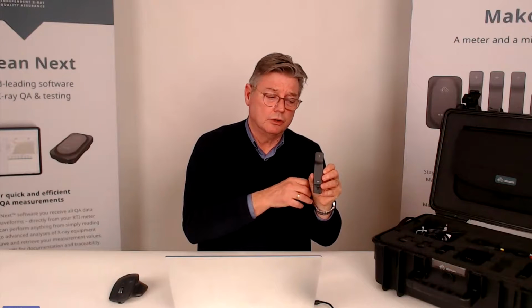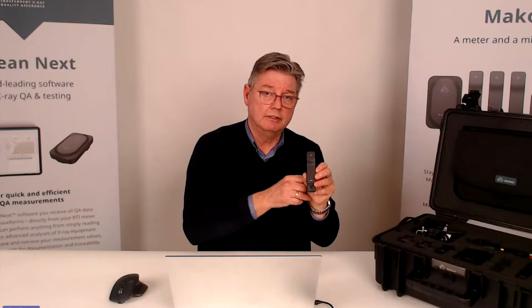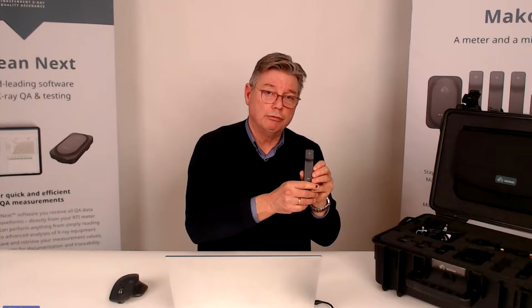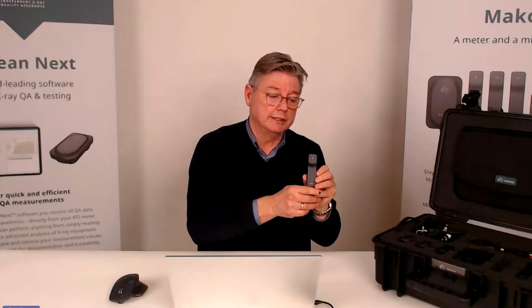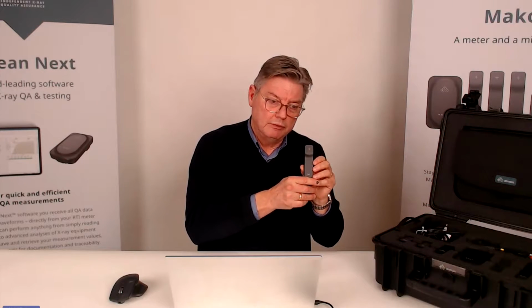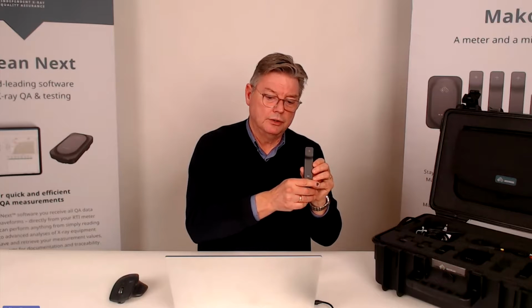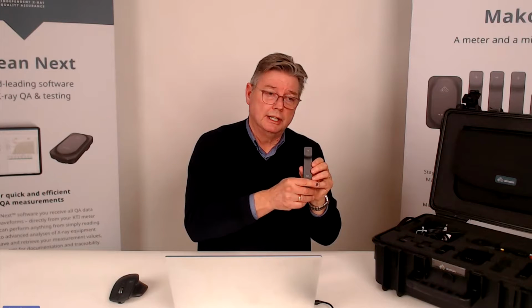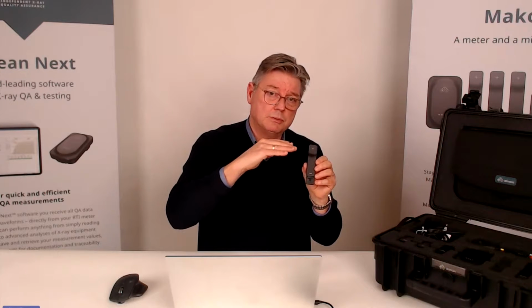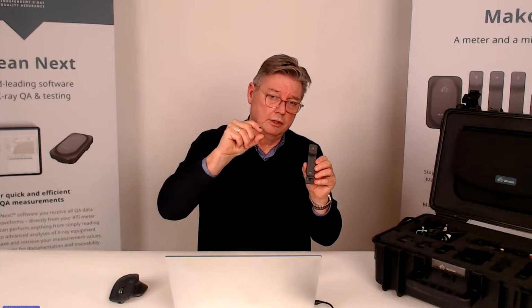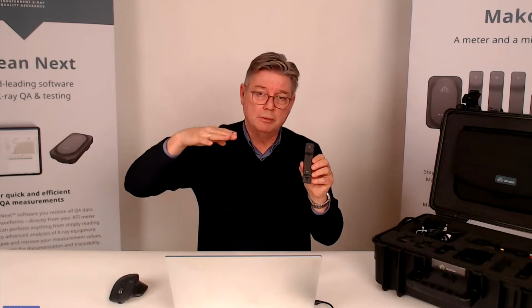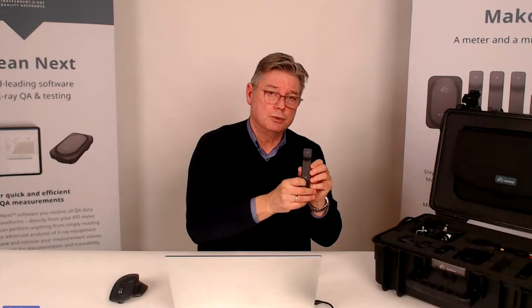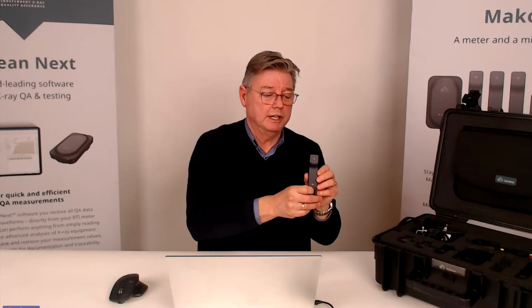And the interesting thing is, across that full range, the accuracy for kV is 1.5% on the kVp, which is quite astonishing. We've also found that the algorithm provides stability in the measurements, so that consecutive measurements are kept within a very narrow band, so it doesn't jump back and forth. It's reproducible and repeatable, the measurement values.